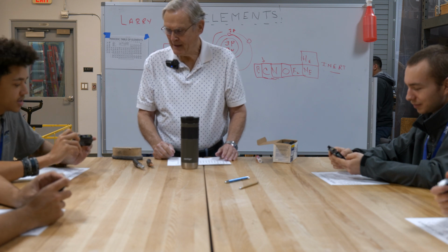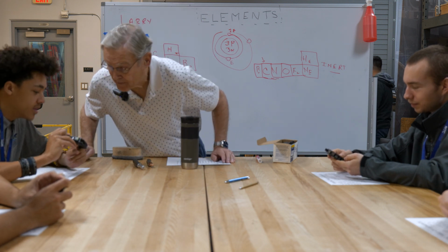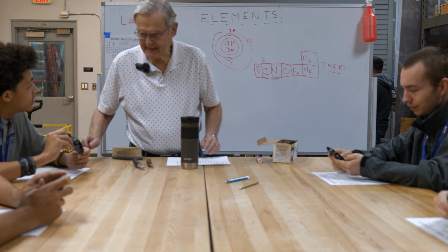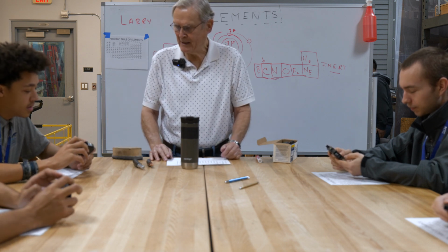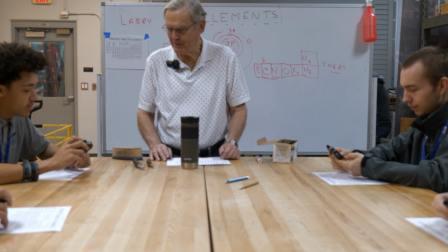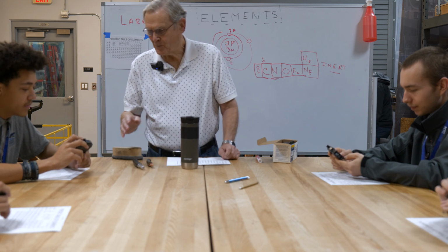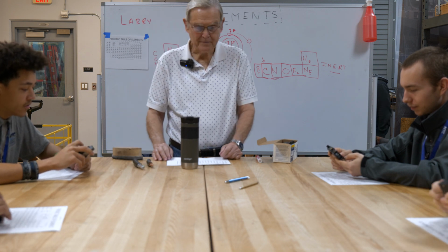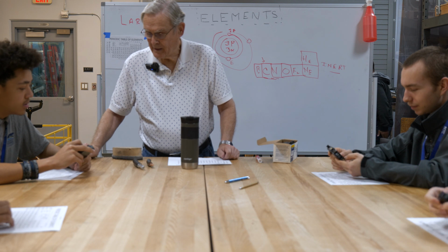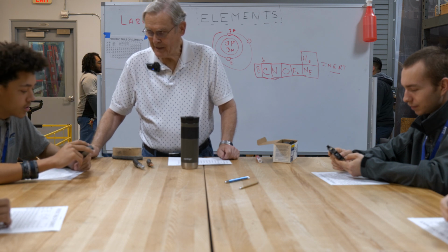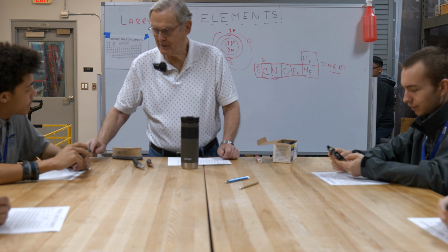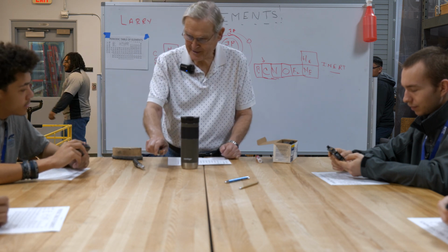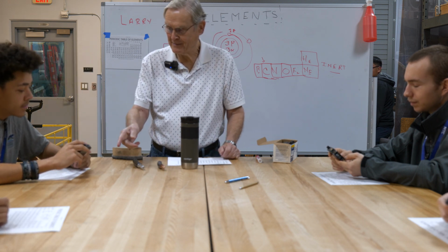So read the nameplate data is what I'm suggesting. Is this the degrees, the 60 and 75? 60 and 75 degrees, that's the temperature rating for the cable that you're going to be using when you go to fabricate the panel. That's just in general. So you see a copper, and you also see aluminum.